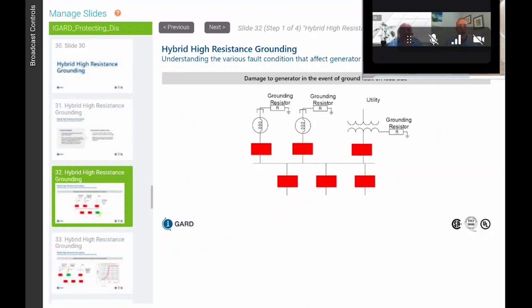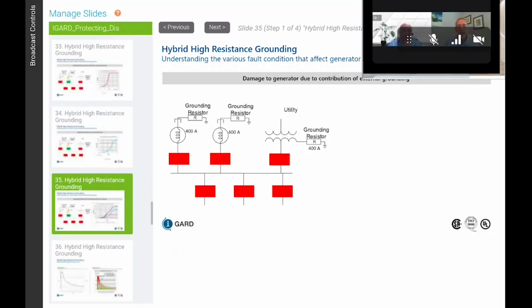Without adding an NGR to all the generators, to minimize ground fault current? Well, the only way to minimize ground fault current is to put an impedance in the return path. So it's either going to be a resistor or an inductor. So I don't know how you're going to minimize ground fault current. Was that what you wanted to minimize, the ground fault current? Yes.